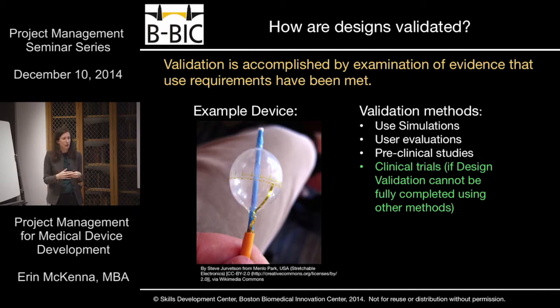You might be doing some preclinical work. You might do an animal functional study to show that your device will treat something that is considered a reasonable comparator to a human disease. And really, clinical trials should be considered a form of design validation. They're a direct form, where you actually measure the effect of the device. For most devices, you're typically not doing a clinical trial unless you just can't answer the question of whether it will do what you need it to do using the other methods.